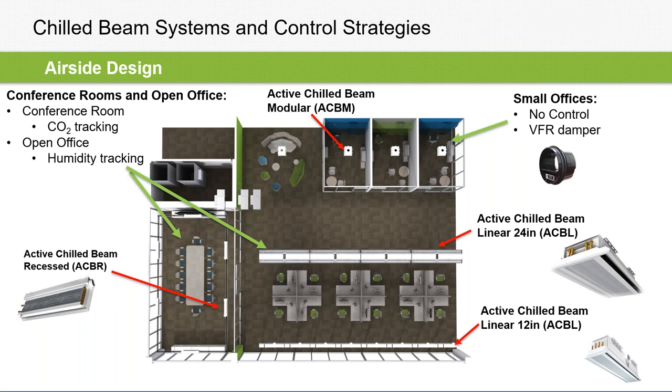So what we would like to recommend, and this is what I would push, is that you would have one or two humidity sensors on the floor. You would be watching those humidity sensors, and you also use the temperature sensor in the space. You would then calculate for dew point. And if you're basically at the dew point temperature in the space, an alarm would go off. Or you could set it to absolutely close the valve on the beam, which would prevent the beam from sweating.